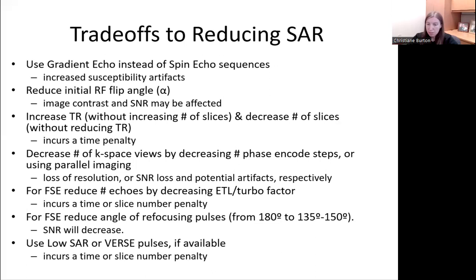Specifically for fast spin echo, the SAR can be reduced by decreasing the echo train length, ETL, which will incur either a time or slice number penalty. Or reduce the angle of refocusing pulses from 180 to 150 or 135, which may reduce the signal-to-noise ratio. You can also use low SAR or variable rate selective excitation pulses, otherwise known as VERSE, if they are available on the scanner. However, be aware that this will incur a time or slice number penalty.